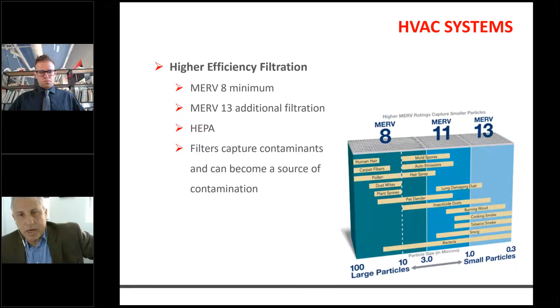Viruses are less than 1 micron and require a higher level of filtration, MERV 17 or better. Your HEPA filters, those are even more difficult to implement in a retrofit application. Even in new construction, the pressure drop, the fan sizing, the first cost and operating costs can be pretty high. Carbon filtration is something typically that was done on outside air for VOCs and odor and smoke control, not really effective with viruses and coronaviruses.